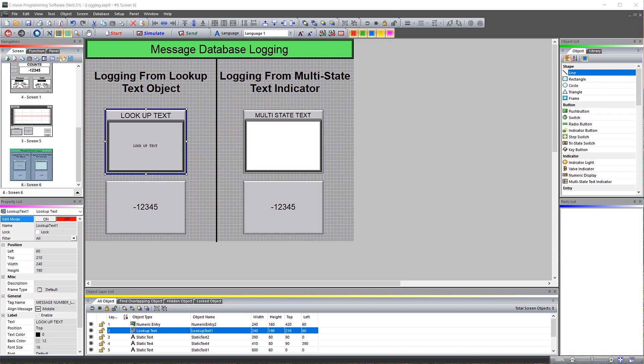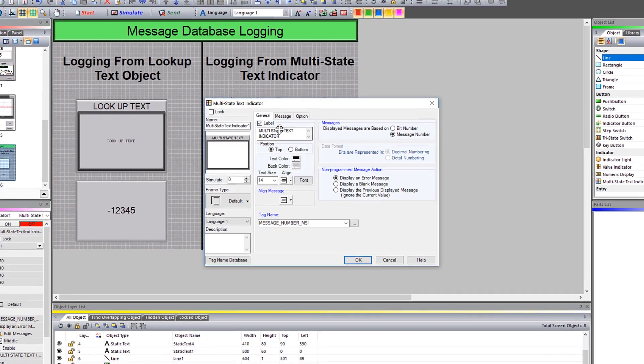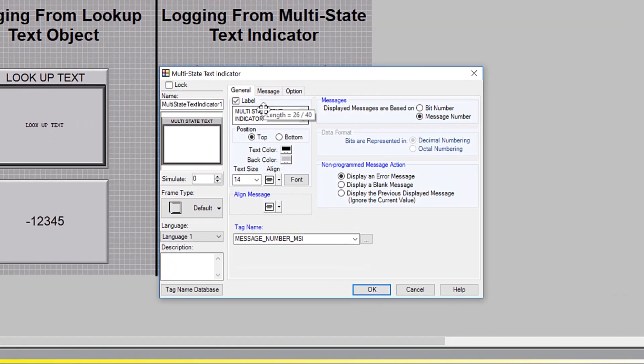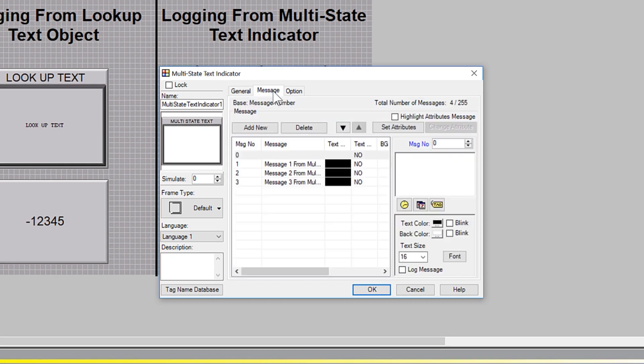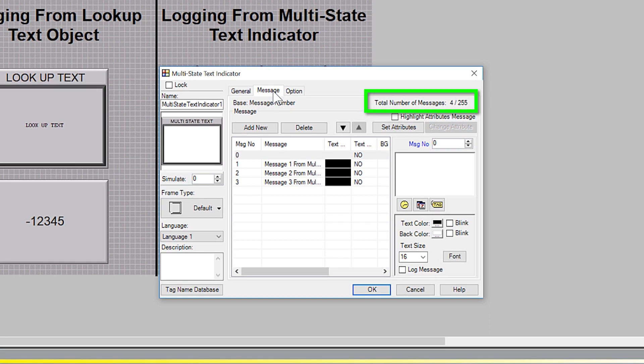This is the main difference when using the Multistate Text Indicator. The Multistate Text Indicator functions basically the same as the Lookup Text Object, but with each Multistate Text Indicator, it has its own list of messages specific to that object. If we look at the Multistate Text Indicator message option, you can create up to 255 messages per object.